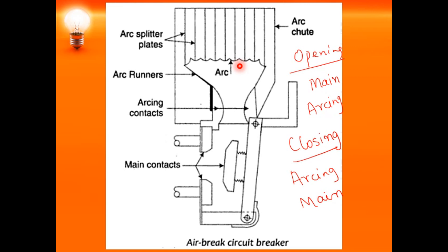In air break circuit breakers, air is at atmospheric pressure. They are used in DC and AC circuits up to 12 kV and are suitable for the control of power station auxiliaries and industrial plants. Since air is at atmospheric pressure, no compressors are needed, and since there is no arc quenching medium like oil or gas, there is no need for replacement. The fire hazard is also not present. They can be used up to 12 to 15 kV.